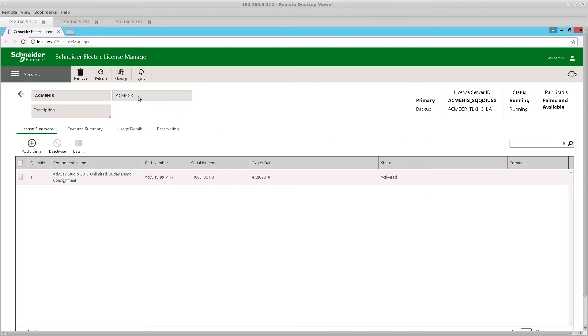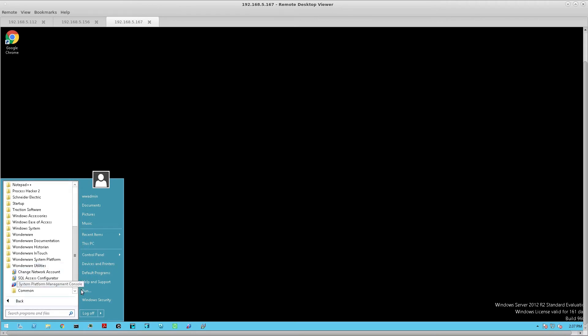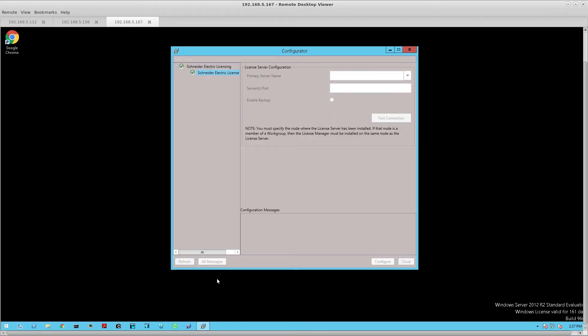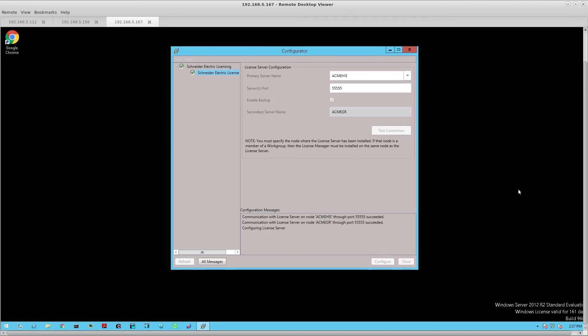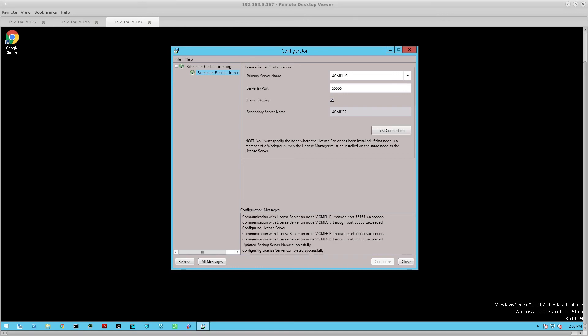Now let's configure one of our Wonderware nodes to point to a primary and a backup system. This is a Wonderware node serving as an InTouch HMI node, so I'm going to open up the configurator utility. I can see that it's already pointing to the primary, so now I'm going to enable the backup. You'll see it's already populated with the backup server name. I'll test the connection — the connection to both the primary and the backup has succeeded — and simply click Configure. Once the configuration is successful, it'll show in the log.